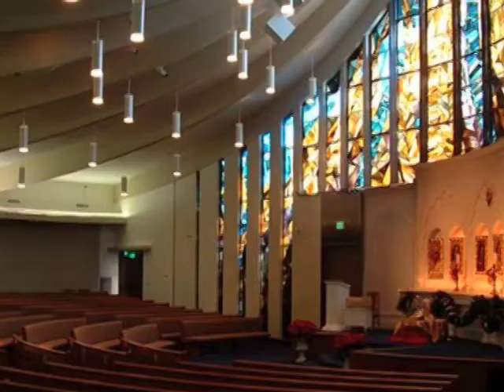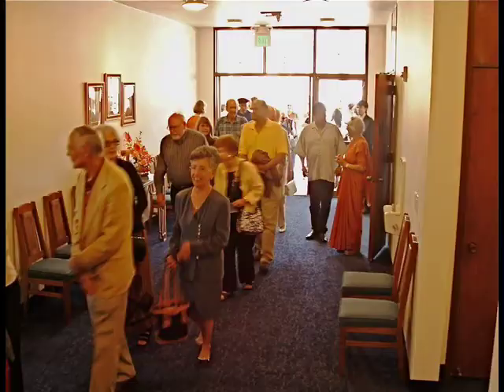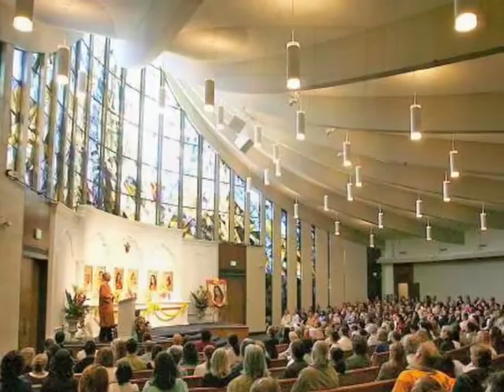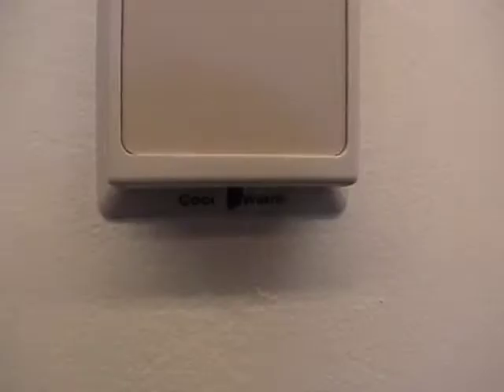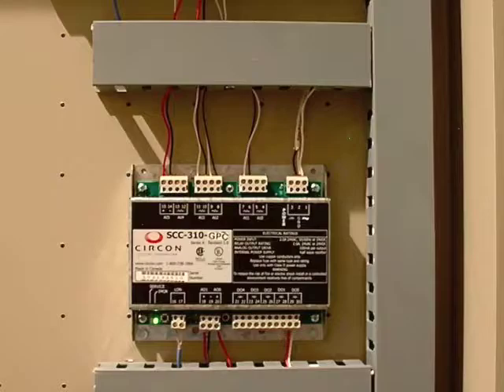Indoor air quality was of primary importance for the sanctuary room, which was occupied by just a few people, to sometimes nearly 500. Noise levels from the mechanical equipment must be kept to a minimum while maintaining high levels of comfort and ventilation. And energy efficiency was an essential requirement as a facility where occupancy rates varied considerably and the central plant must be able to precisely match the dynamic load conditions.